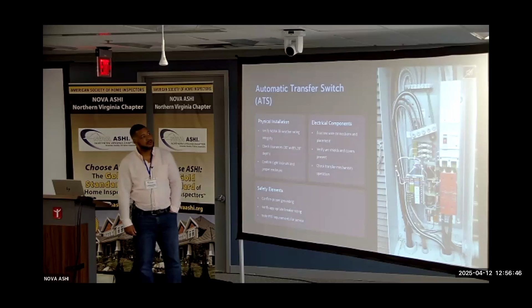So one of the things in this ATS, I was like, why are there so many different grounds up there? If we start counting them up at the top, you have the one from the generator. You have the one going back to the panel. You have the grounding electrode. You have the cold water, and then you have a third one. And as you just mentioned, for the gas that has that CSST, that's why you have that third ground there. So it came here to this ATS.